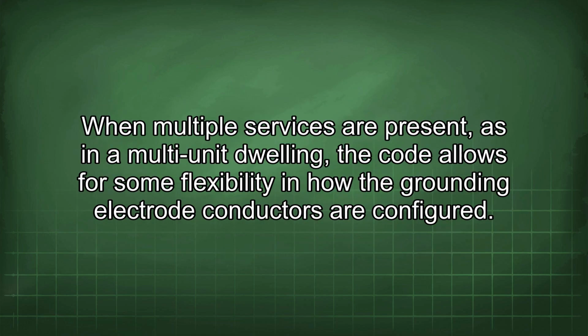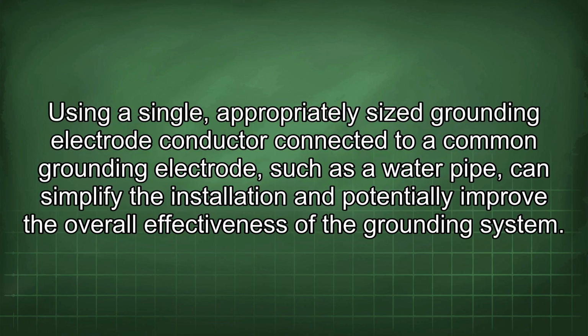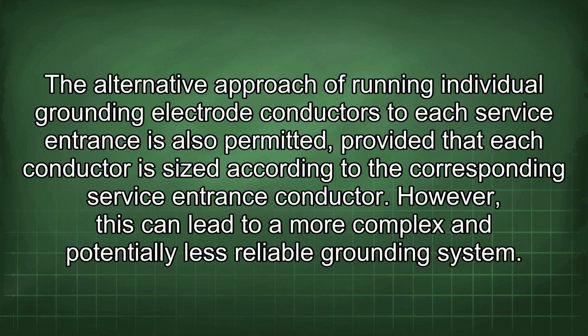When multiple services are present, as in a multi-unit dwelling, the code allows for some flexibility in how the grounding electrode conductors are configured. Using a single, appropriately sized grounding electrode conductor connected to a common grounding electrode, such as a water pipe, can simplify the installation and potentially improve the overall effectiveness of the grounding system. The alternative approach of running individual grounding electrode conductors to each service entrance is also permitted, provided that each conductor is sized according to the corresponding service entrance conductor. However, this can lead to a more complex and potentially less reliable grounding system.